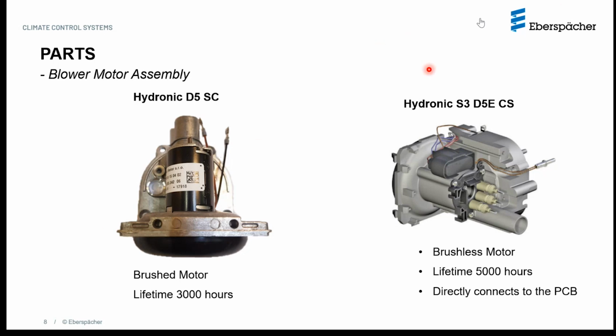Anyways, on this slide we are going to talk about the parts, and the way we are looking at the parts is basically I've arranged them on either side. One is the older unit and the newer unit, so the first generation and the third generation. So as I mentioned, this is the blower motor, which is a brushed motor with an estimated service life of 3,000 hours. Whereas now the newer generation is a brushless motor, with an estimated service life of 5,000 hours. And a couple of things, this unit directly connects to the PCB board on that ECU of the heater. Whereas over here we have the harness and terminal pins that will pin into the connector, and the connector is plugged into the ECU. So this is more direct, whereas this is indirect.